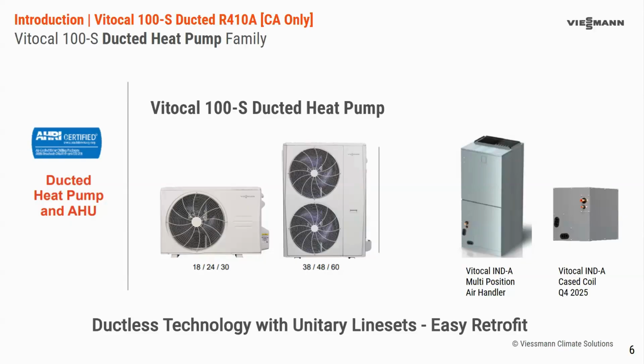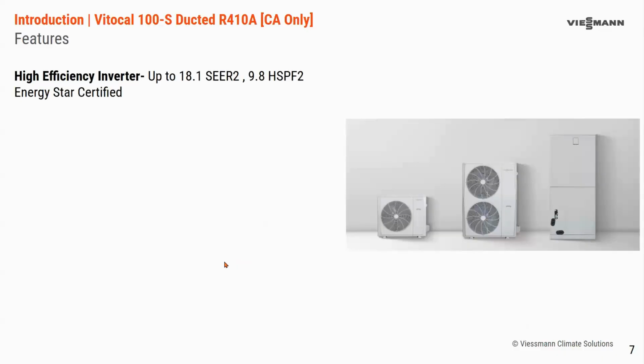So if you're going to a retrofit, you already have a line set there that's insulated only on the suction line instead of having to run an all new line set for a ductless unit and insulate both lines. You now can just pop this outdoor unit and an indoor unit in the place of the previous equipment and install it, and you're good to go. So a little bit more information on that.